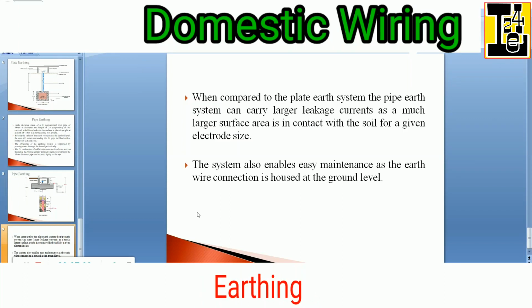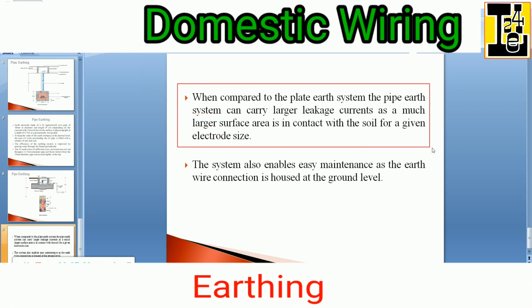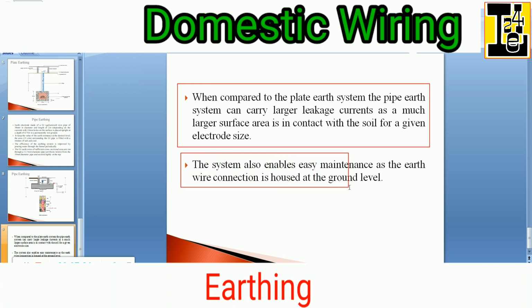When we compare both types of earthing, compared to the plate earth system, the pipe earth system can carry larger leakage currents, as a larger surface area is in contact with the soil for a given electrode size. The system also enables easy maintenance as the earth wire connection is housed at the ground level.